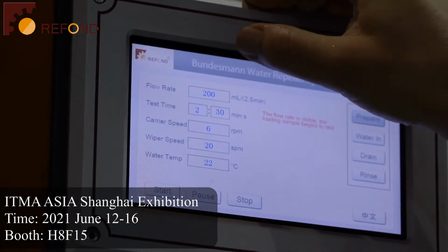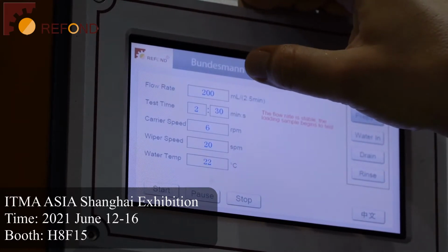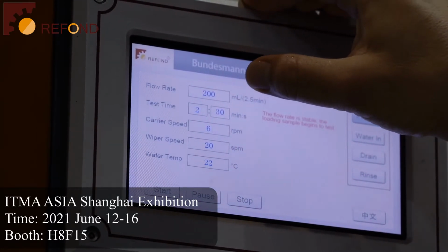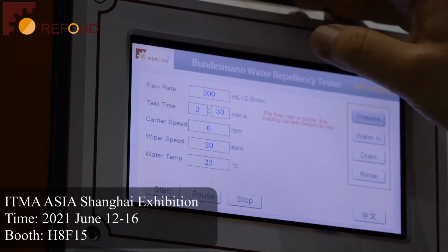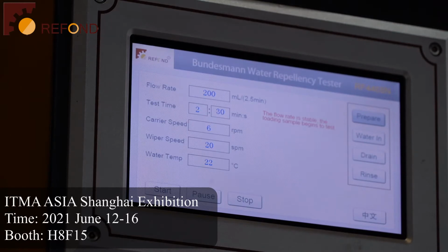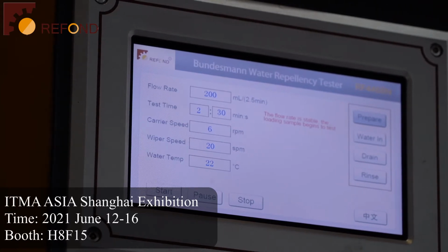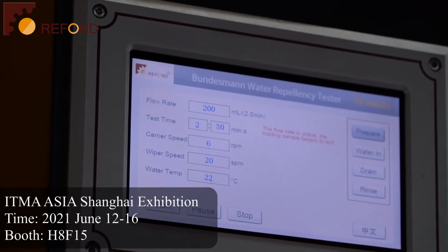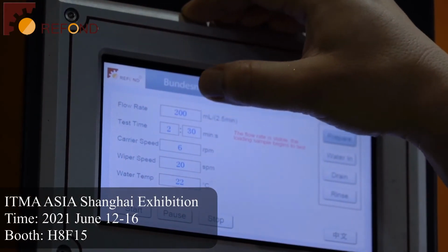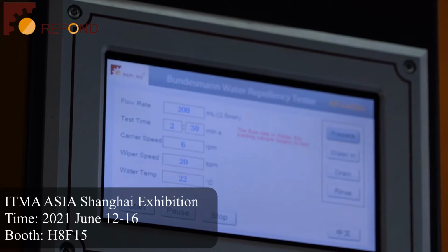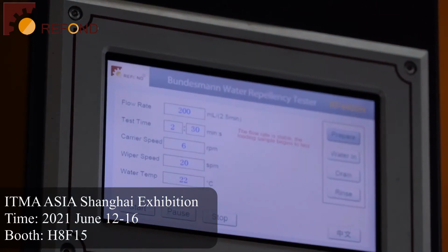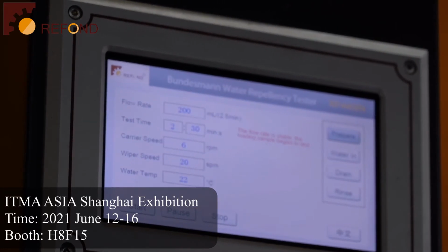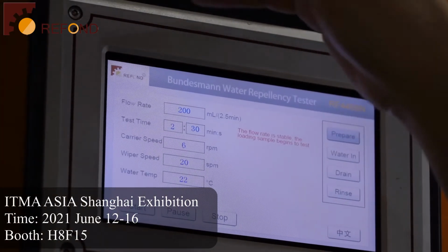In the ISO testing standard, they require the flow rate is 200 milliliters plus or minus 10 milliliters in 2.5 minutes. In the old model of the testing machine, it is very hard to adjust the actual flow rate. In our new machine, we have the advanced technology. It can control the flow rate automatically to a desired level. Because we have built in the pump and the flow sensor inside this pipeline, it can control the water circulation and control the flow speed.